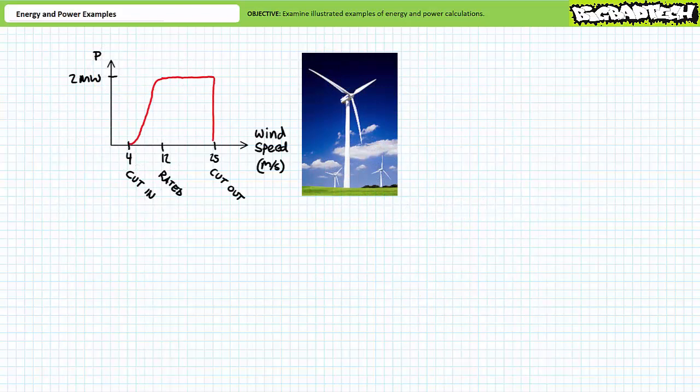Power need not be constant nor linear. Consider the power curve for an industrial wind turbine — a graph of power output at different wind speeds. This example assumes the wind turbine has a nameplate rating of two megawatts. A power curve is defined by three points: the cut-in wind speed, the rated speed, and the cut-out speed. The cut-in speed, typically around four meters per second, is when the turbine starts producing power. At the rated speed, typically around 12 meters per second, the turbine generates its nominal two megawatt value. Between rated and cut-out speed, power flatlines at the nominal value. At the cut-out speed, typically around 25 meters per second, the turbine shuts down to prevent mechanical damage.